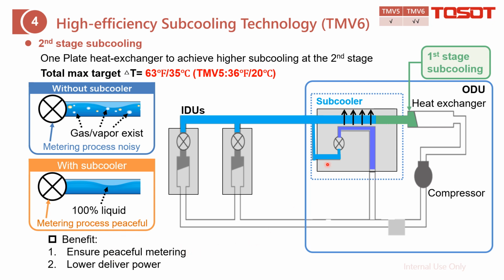On the other hand, if it contains a little bit of gas, it will also cost more power to deliver the refrigerant from outdoor to indoor, and this power comes from the compressor. In other words, if we can make it cooler, it can also lower the compressor power. For our latest TMV system, we can achieve the delta T, which is the margin away from it becoming gas or vapor. This one we claim to be 35 degrees Celsius.